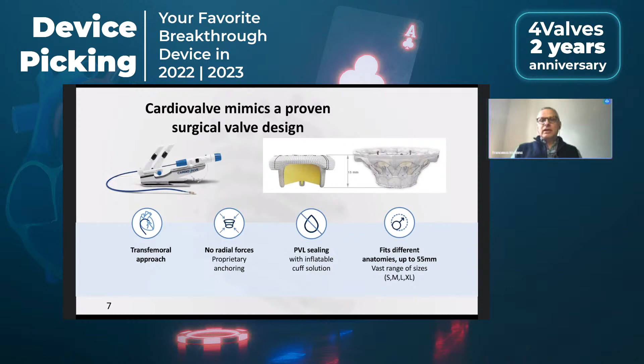First of all, it doesn't need a lot of radial force to be implanted, and that brings you two major advantages. Advantage number one, it allows the valve to sit also in large anatomies, and also it allows some degree of reverse remodeling of the base of the ventricle. Imagine if you block the base of the ventricle with a very strong device which needs some radial force, you are going to impact also ventricular strength. And finally, having little radial force needed is probably protective from pacemaker implantation. We have seen other devices have been associated with a large number of pacemaker implants. Cardiovalve, still limited experience, not even 20 patients done till now, but only one patient received the pacemaker afterwards.